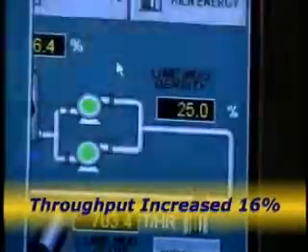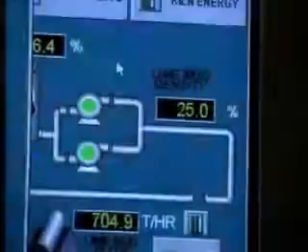In fact, it's closed the variability of both the back end and feed end temperatures. So what are the paybacks from those dramatic reductions in process variability? Since we've been running on full control, we have decreased our energy substantially, and we have increased the kiln throughput also by probably around 15–16%. It's running consistent, and the ramping capabilities are really, really good as far as mud feed rates.